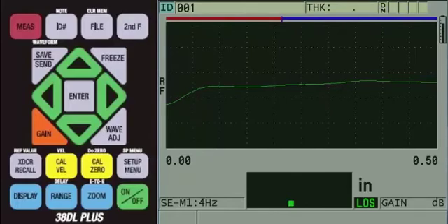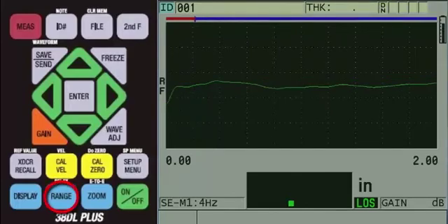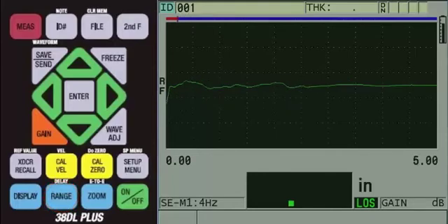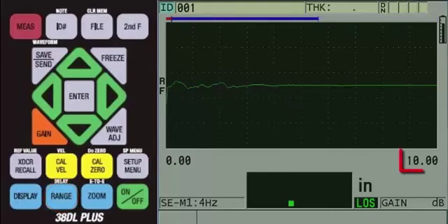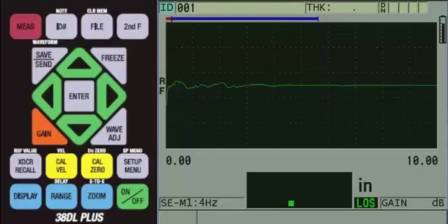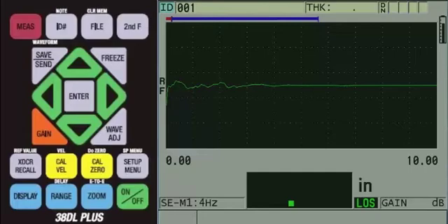To change the range, keep pressing the blue RANGE key until the bottom right side of the screen displays 10.00. If you are using metric units, it will be set to 200.0. We set our range based on our thickest step, which is 4.685 inches or 119 millimeters. If we set our range so we can see the back wall echo from the thickest step, then the back wall echoes from the thinner steps will appear sooner in time and be displayed on screen.